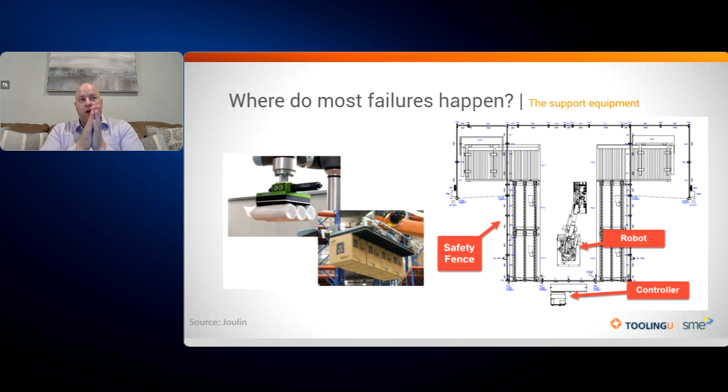I've seen times where the conveyor itself, so the robots have what's called a tracking method. That's if the product is moving down the plane of the conveyor and the robot has to follow it and then pick it. So I've seen cases where the conveyor has stretched and the robot may be delayed in its picking. So these are all the different things that happen.